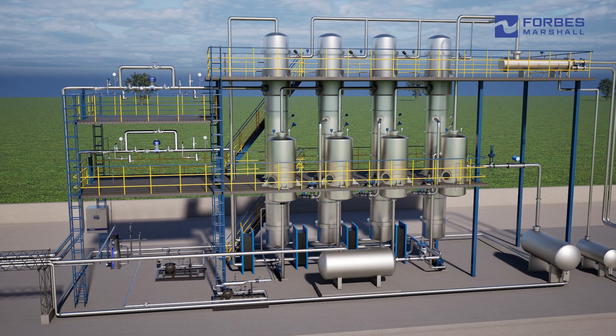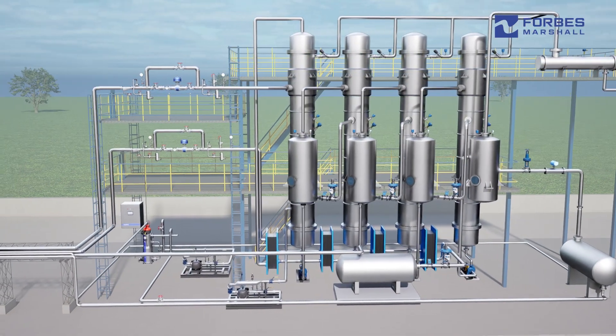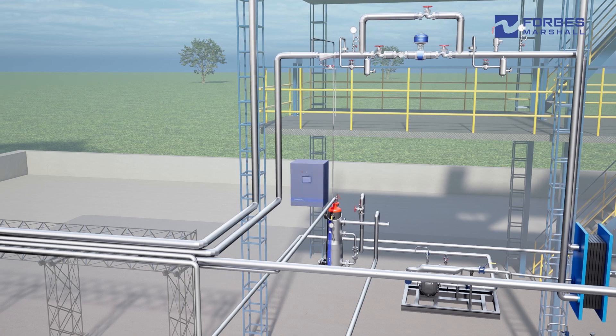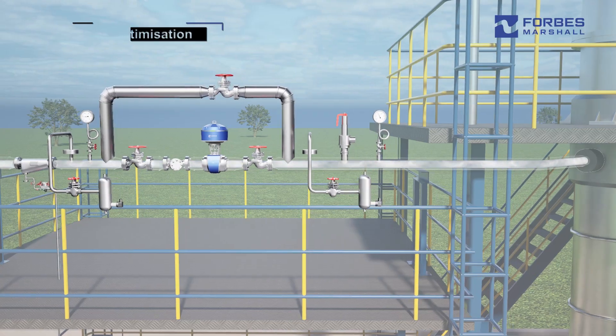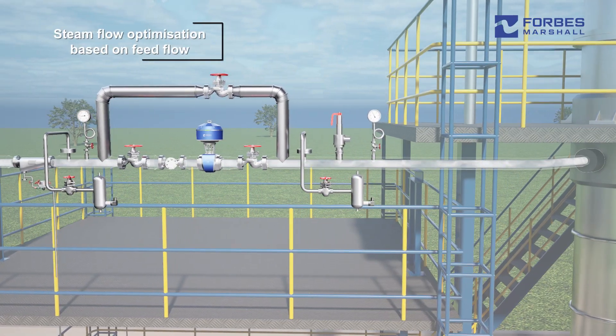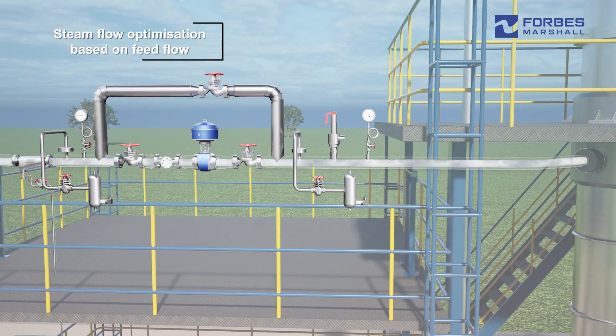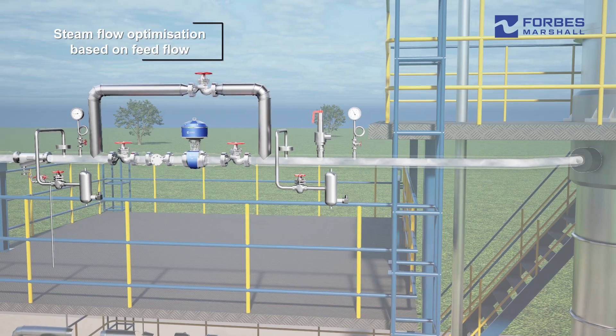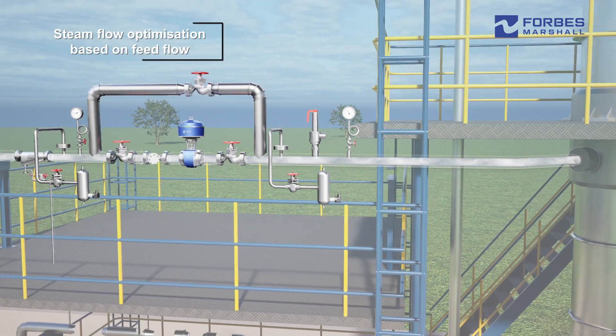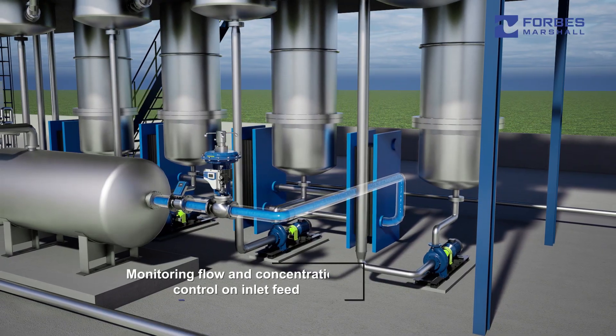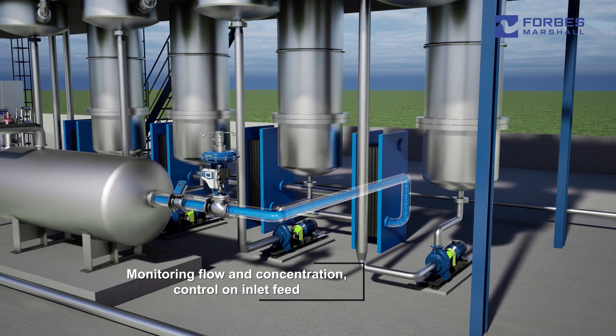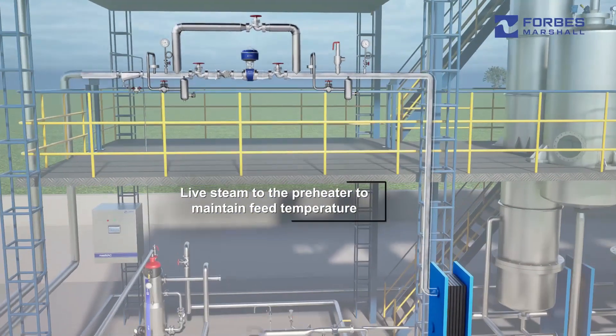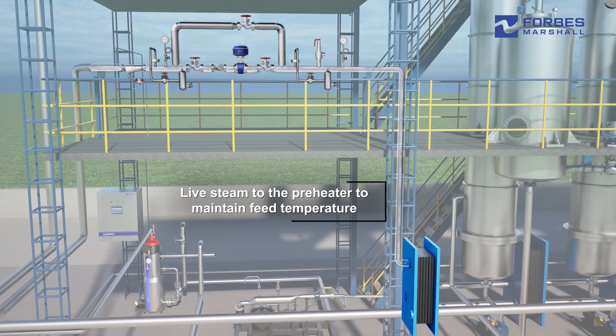Forbes Marshall provides a holistic solution designed to enhance and manage evaporator performance. The control philosophy focuses on proactive modulation of key parameters in response to dynamic variations. Steam flow is optimized for each feed flow range to achieve optimal steam economy while ensuring desired evaporation, product specific gravity, and consistent calandria levels. Inlet feed is monitored for flow and concentration, and a steady feed flow is maintained.